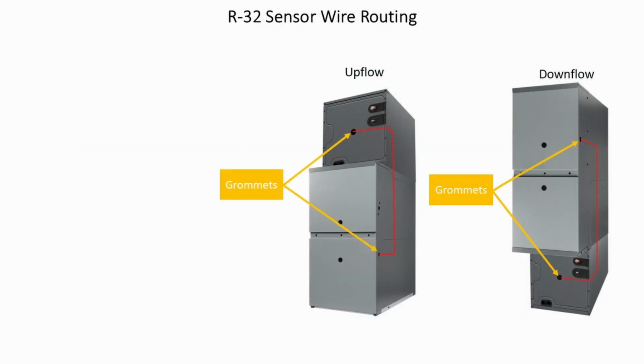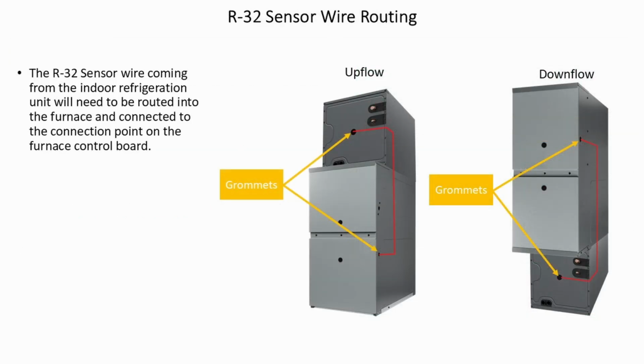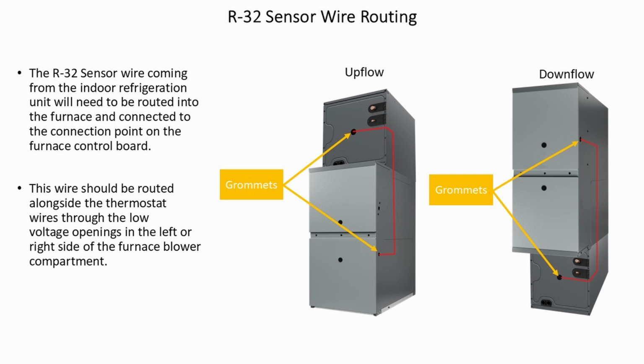R32 sensor wire routing. The R32 sensor wire, coming from the indoor refrigeration coil, will need to be routed into the furnace and connected to the connection points on the furnace integrated control module. The wire should be routed alongside the thermostat wires through the low voltage openings in the left or right side of the furnace blower compartment.